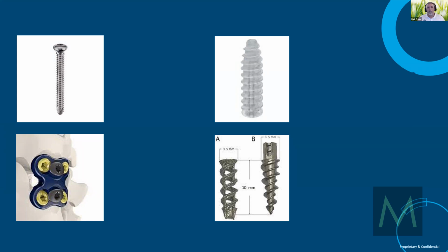So according to 21 CFR 820.75, if the outcome of a process cannot be verified, it must be validated. So a lot of these things, there's too many small parts, like screws, for instance, is a really good example. And your biocompatible one there that would be absorbable is a great example, and the spinal one too, because I've worked in spinal processes. Natural manufacturing variability is something you have to take into account to understand your success rate, because you can't just say, oh, okay, they made it.